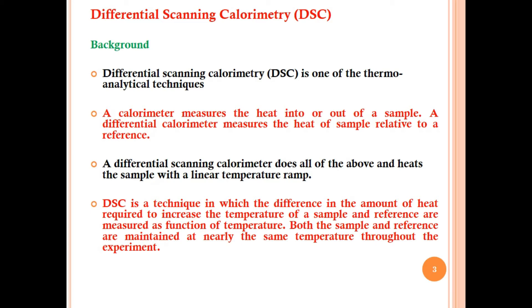Let's see the background of DSC. Differential scanning calorimetry is one of the thermoanalytical techniques. A calorimeter measures the heat into or out of the sample. A differential calorimeter measures the heat of a sample relative to a reference. Differential means a difference — the calorimeter measures the difference between the sample and the reference. A differential scanning calorimeter does all the above and heats the sample with a linear temperature ramp.